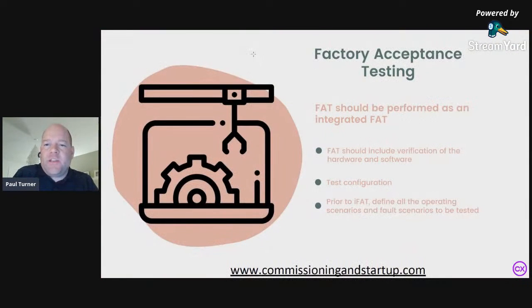Now, when you get to factory acceptance testing, I can't stress enough how important this is as part of the commissioning phase. Lots of people might think that this is an earlier activity that precedes commissioning, as maybe handled by the design team, and the commissioning team doesn't need to get involved, but that's not true. This is definitely a critical step of the commissioning process. And the focus needs to be on the hardware and the software. The factory acceptance testing can't be just a verification of the hardware. It needs to also incorporate the code that has been simulated to prove that both the hardware and the software function correctly. Doing this earlier in the project and proving the software at this point in time is immensely valuable to the commissioning phase later.